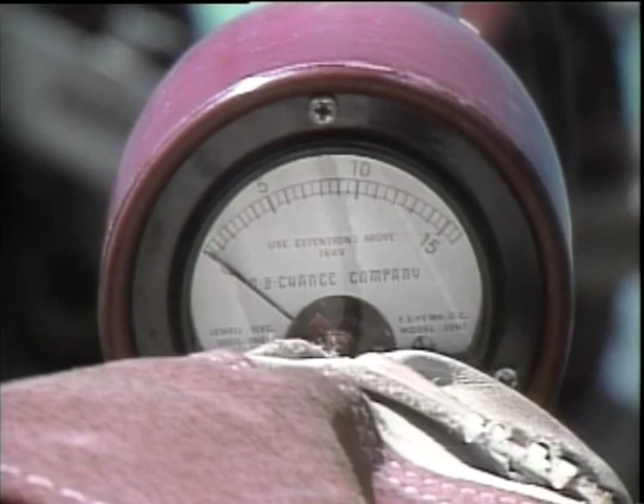If the tester works properly, the meter measures phase to ground voltage. Now the circuit can be tested for dead. With one hook on an established ground, the other is placed on the phase line you're testing. A zero reading for this line indicates there is no measurable voltage present.